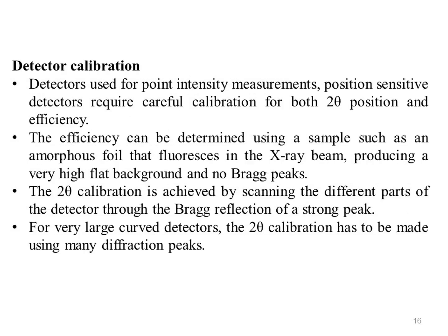And now is detector calibration, which is a more important step. In contrast to detectors used for point intensity measurement, position sensitive detectors require careful calibration for both 2 theta position and efficiency so that scattering angles and intensity can be accurately determined.